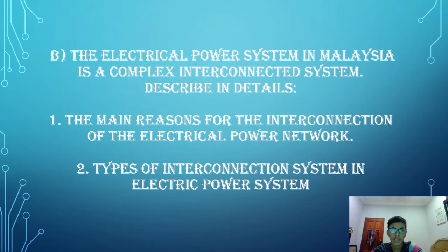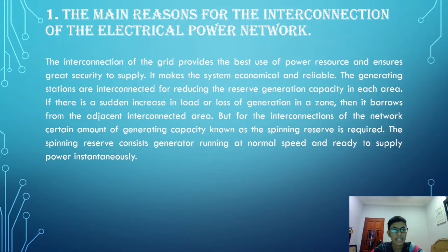Okay, number one, the answer is the interconnection of the grid provides the best use of power resources and ensures great security of supply. It makes the system economical and reliable. The generating stations are interconnected for reducing the reserve generation capacity in each area. If there is a sudden increase in load or loss of generation in a zone, then it borrows from the adjacent interconnected area. But for the interconnections of the network, a certain amount of generating capacity, known as the spinning reserve, is required. The spinning reserve consists of generators running at normal speed and ready to supply power instantaneously.